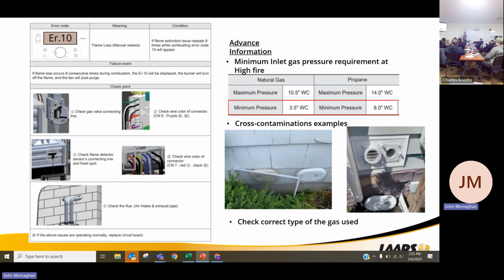The troubleshooting unit, again, it's going to have a listing of error codes with it. Basically, it's going to follow what the FT series is. Error 10 is going to be a flame loss. Goes through how to check it. Look for any of your issues, whether it's cross-contaminating, whether you have loss of flame due to running out of fuel. And again, it's a 199,000 BTU gas appliance. Oftentimes, when we're swapping this out, we're removing a 40,000 BTU gas water heater.